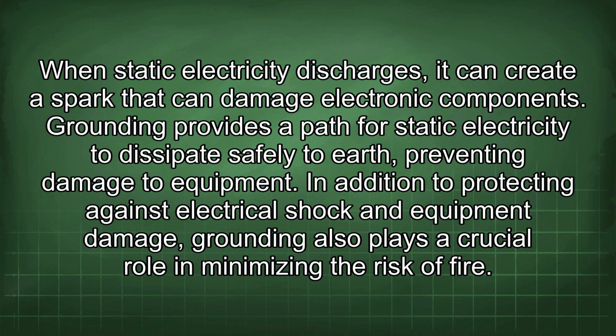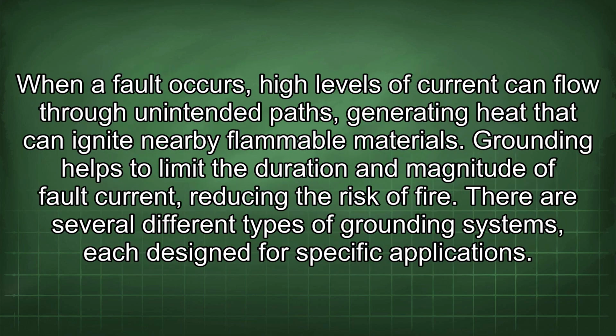In addition to protecting against electrical shock and equipment damage, grounding also plays a crucial role in minimizing the risk of fire. When a fault occurs, high levels of current can flow through unintended paths, generating heat that can ignite nearby flammable materials. Grounding helps to limit the duration and magnitude of fault current, reducing the risk of fire.